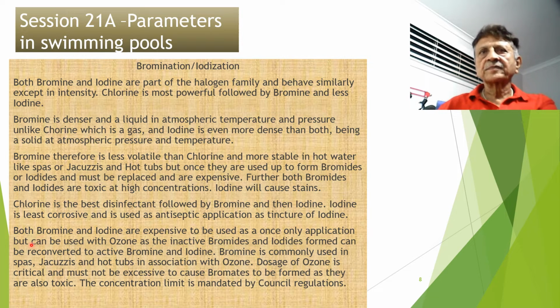But when we use them with ozone, the inactive bromides or iodides formed can be reconverted to active bromine and iodine. Bromine is more commonly used in spas, jacuzzis and hot tubs rather than iodine. The reason iodine is not used is that it tends to stain the tubs. The dosage of ozone is critical when it is used with bromine, because excess ozone may cause bromates to form. In other words, the bromide forms bromine with ozone, but this bromine may react further with ozone to form bromates. And these are toxic. Therefore, the concentration limit is mandated by council regulations.